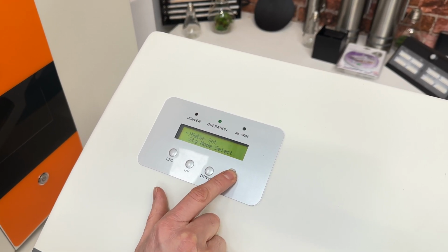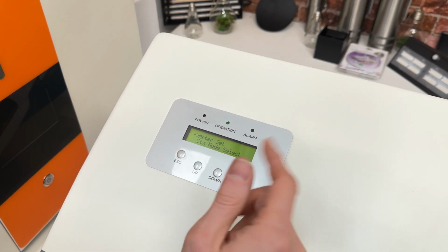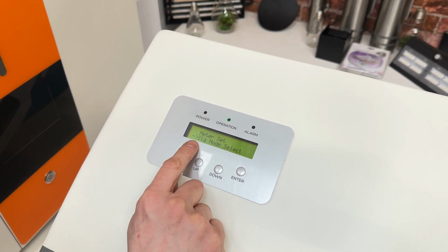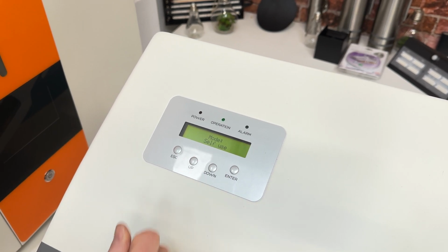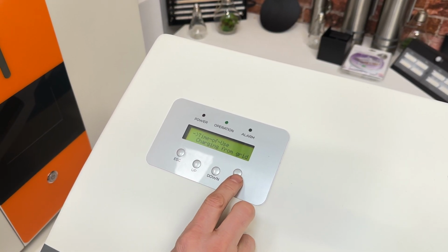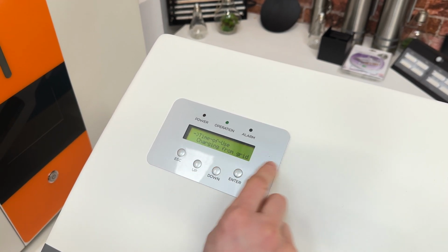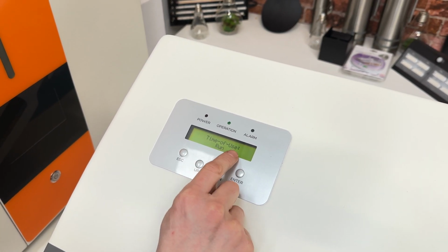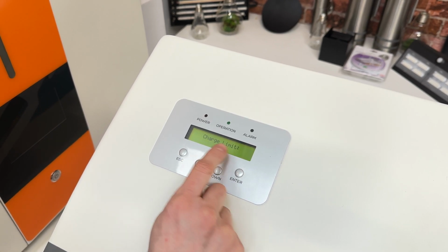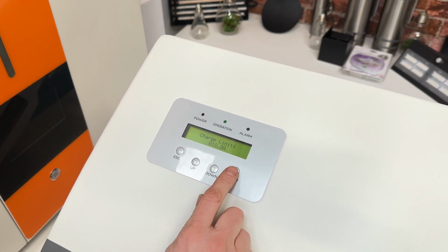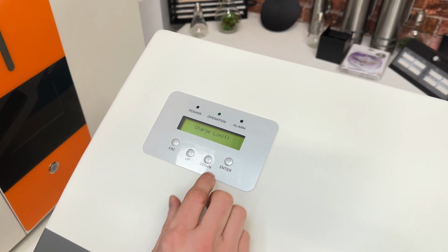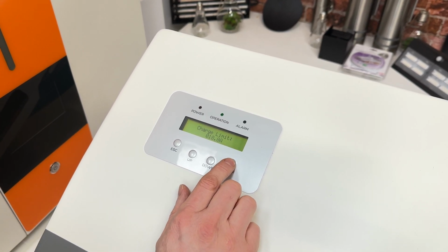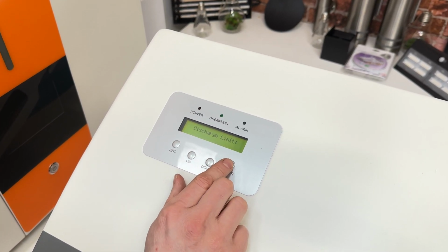Then we scroll down to storage energy set. The meter set is external meter with current sensors. STG mode select, self-use. It is on. The time of use, charging from the grid, we set it to run. We set the charge limit, that is only a few amps, 10 to 20 amps. It's a low current, high voltage system. The discharge limit, the same.